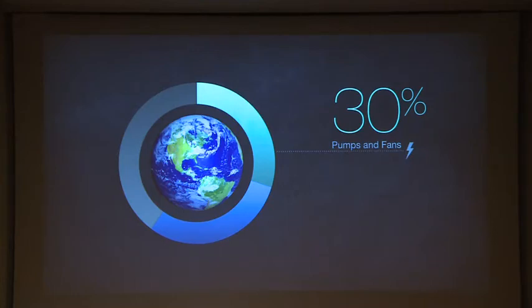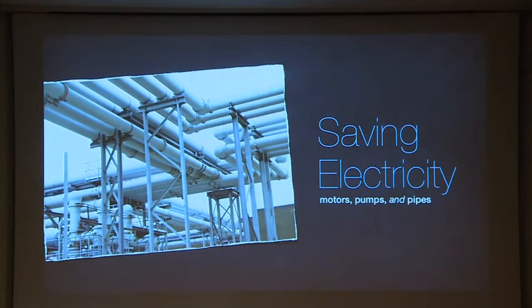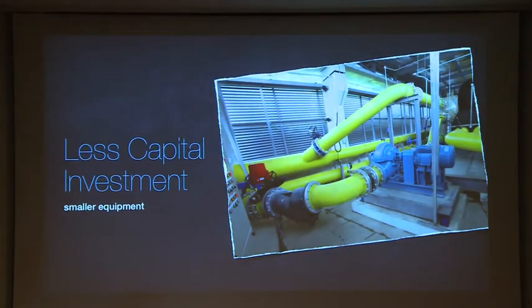For example, pumps, the biggest use of motors, move liquid through pipes, but a standard industrial pumping loop was redesigned to use at least 86% less pumping energy, not by getting better pumps, but just by replacing long, thin, crooked pipes with fat, short, straight pipes. That also shrinks the pumping equipment and its capital costs. So this isn't new technology, it's about rearranging our metal furniture to apply and combine better the technology that we have.